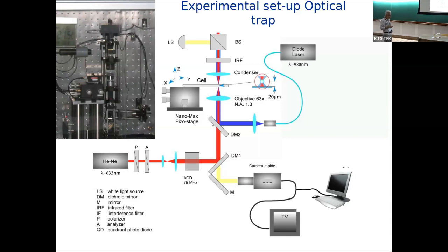The point is the following: one laser is used for the trapping, and the other has a very much smaller power than the one that is trapping, and is used for detecting very fast displacement of the particle. The laser goes through the particle, which is actually acting as a lens. And so when the particle moves, it deflects both lasers, but what we are interested in is the small power laser, which is just refocused correctly. And then on the top there is a position sensitive detector, which measures the position of the beam as a function of time. And this allows you to measure the position of the particle very precisely. Does it answer your question?